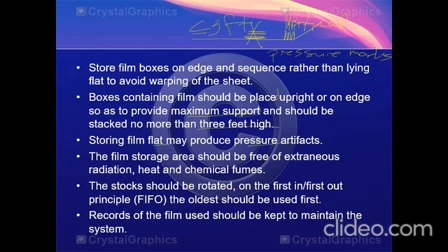The film storage area should be free of extraneous radiation. Pag sinabing extraneous radiation, these are radiation coming from the adjacent room or outside the storage room. Also, free from heat and chemical fumes to avoid spoilage or additional artifacts sa ating film.